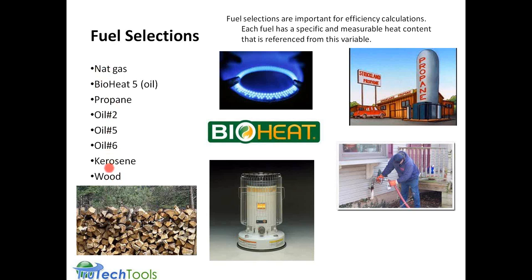These fuel selections will help the meter make the correct calculations for some of the calculated parameters, so you want to make sure this is correct. The fuel selection will appear on the printout. It's also at the top of the combustion analysis screen to make sure you're prompted in the correct mode. You can always change it on the fly, but you just want to make sure you have the correct fuel set, bottom line.